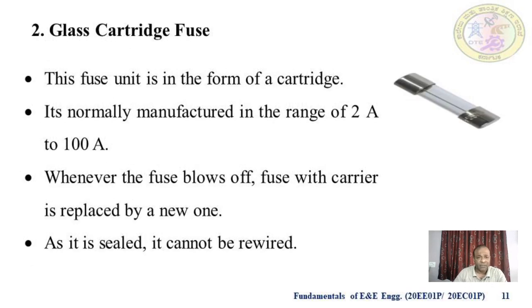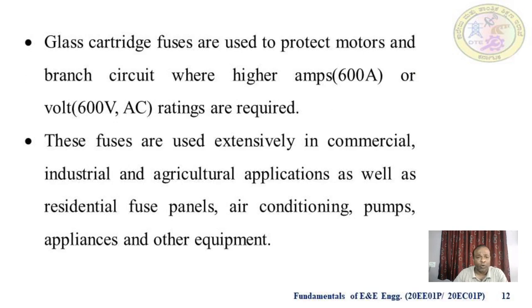The glass cartridge fuse is a form of cartridge fuse, normally manufactured in the range of 2 ampere to 100 ampere. Whenever the fuse blows off, the fuse with carrier is replaced by a new one. As it is sealed, it cannot be rewired. Cartridge fuses are used to protect motors and branch circuits where higher ratings are required, like 600 ampere, 600 volt AC. These fuses are used extensively in commercial, industrial and agriculture applications as well as residential fuse panels, air conditioning, pumps, appliances and other equipment.